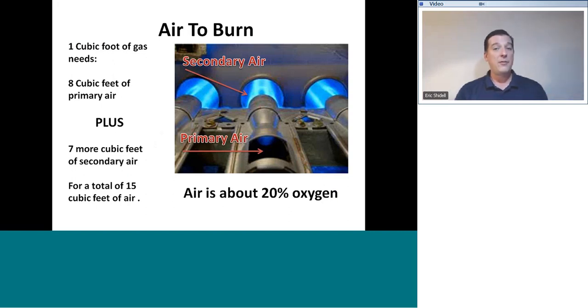That oxygen is going to come from air. We're not using a natural gas and oxygen torch. We're using an air and natural gas mixture. Air is about 20% oxygen. There's a lot of other stuff in air that we don't really need to support the combustion process. If we could just do straight oxygen, we would, but we don't have to because there's enough oxygen in air to support combustion. So our oxygen is going to come from the combustion air supply. We need to think about air whenever we're thinking about burning gas. It's so easy to focus on the gas. We've got to focus on the air too.